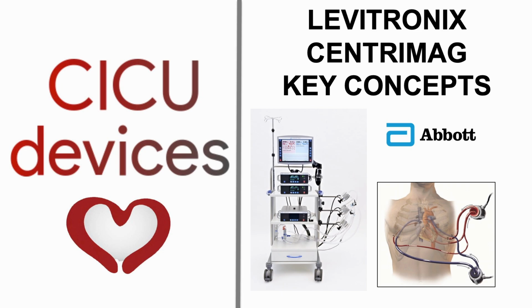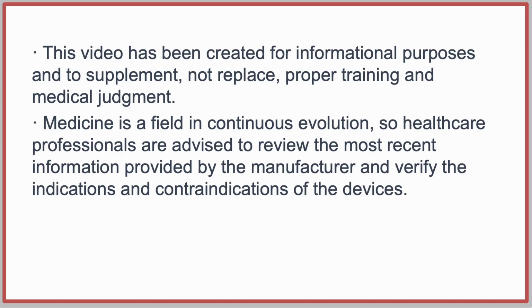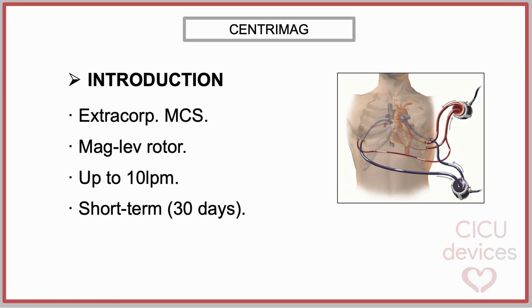CICU devices. Levitronix CentriMag. Key clinical concepts. The Levitronix CentriMag is an extracorporeal temporary mechanical circulatory support system designed for short-term ventricular assistance in patients with acute cardiogenic shock and severe cardiopulmonary insufficiency. The system uses a centrifugal blood pump with a fully magnetically levitated rotor, eliminating mechanical bearings and seals, and thereby reducing friction, wear, and blood trauma. This design contributes to a low risk of hemolysis and thrombus formation and allows reliable high-flow support.